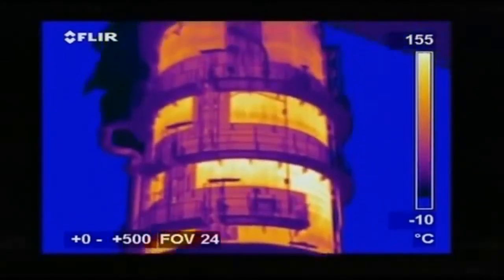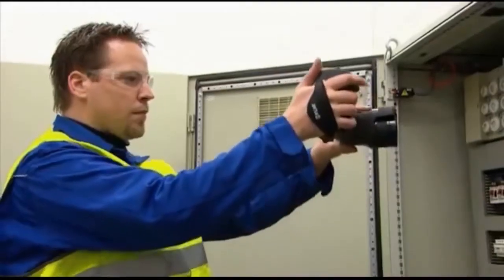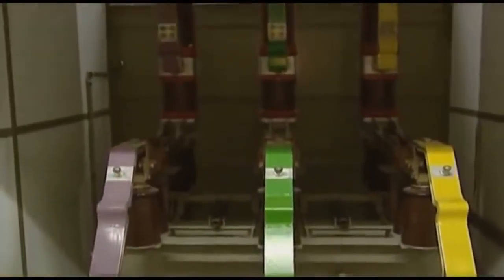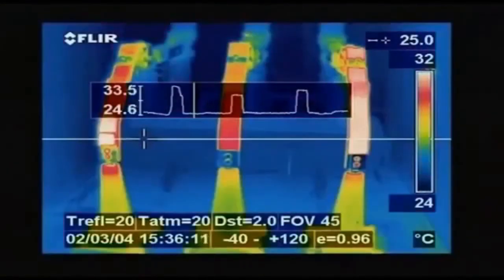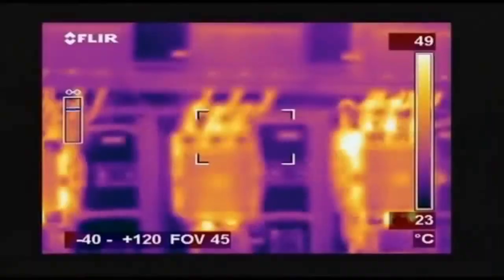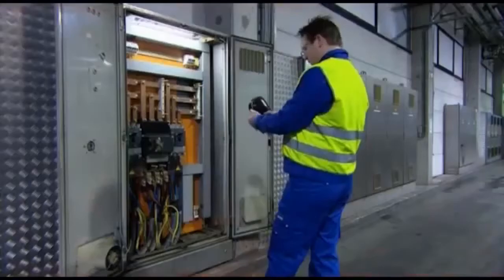Whether you're monitoring high voltage equipment, low voltage cabinets, motors, pumps, high temperature equipment, or looking for insulation losses, a thermal imaging camera is the one tool that lets you see it all. If a low voltage connection breaks down, aside from the production loss there's a greater danger: fire. A small electrical problem can have extremely far-reaching consequences — the efficiency of the electrical grid drops, energy is spent generating heat, and if left unchecked, heat can rise to the point where connections start to melt and sparks can fly, setting the environment on fire.